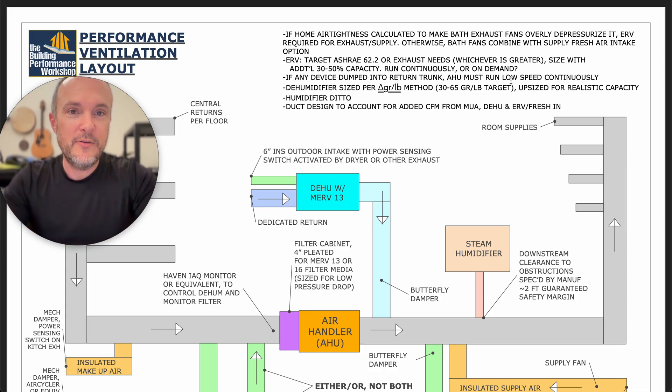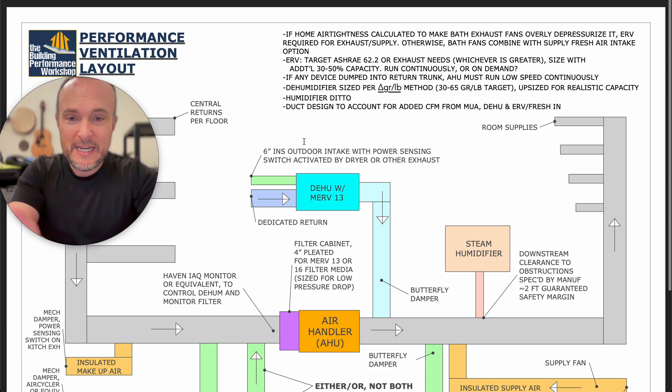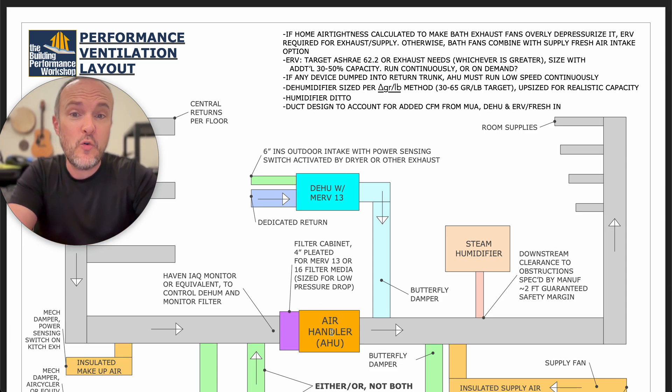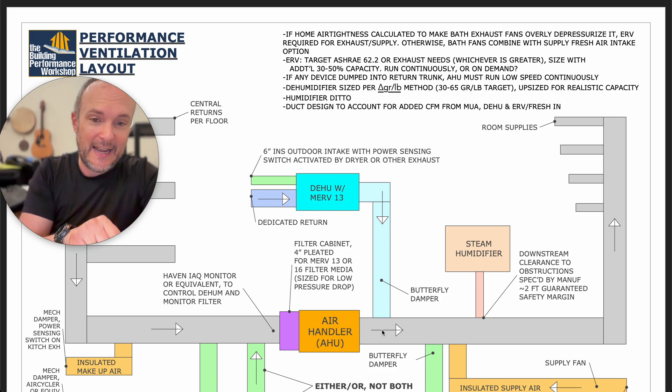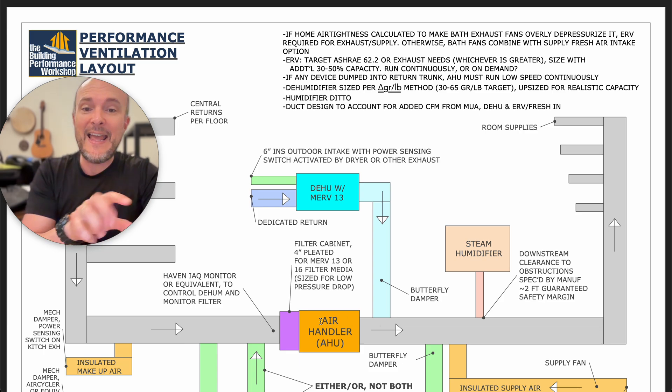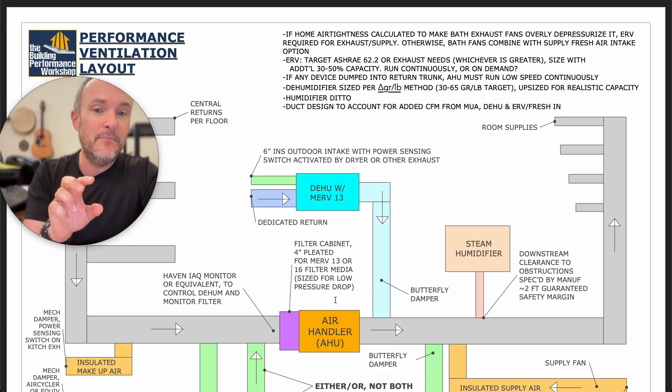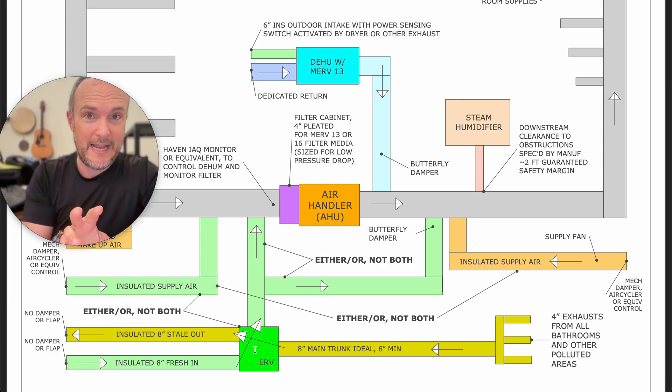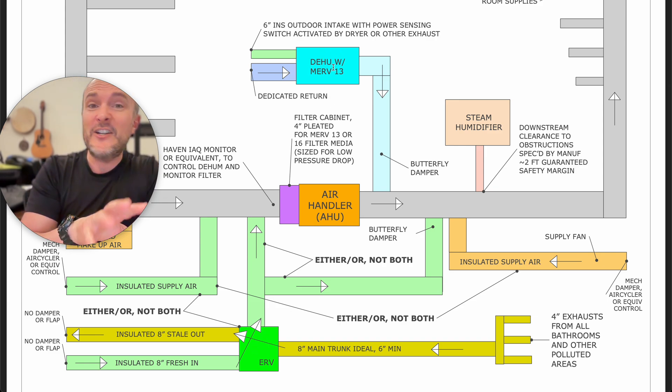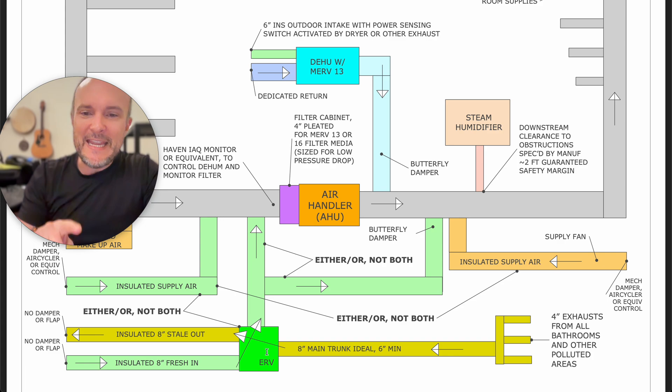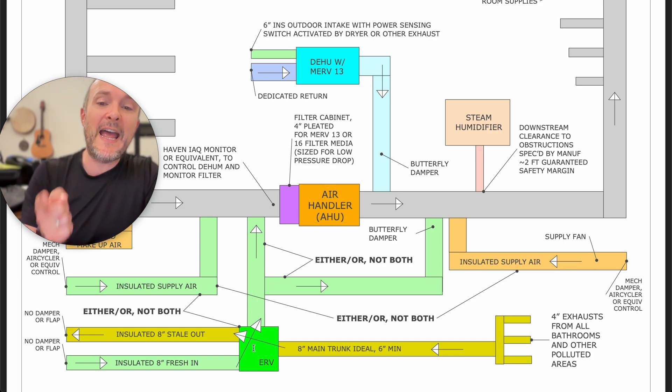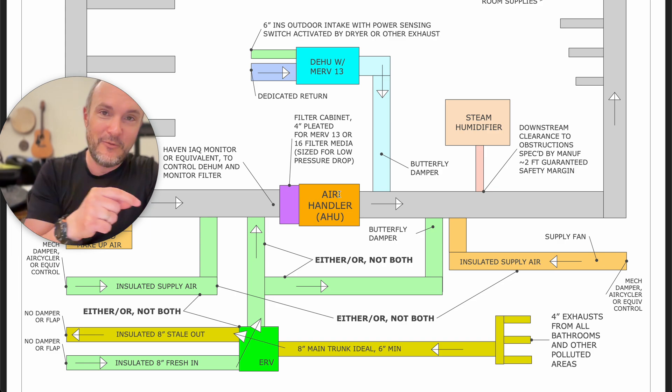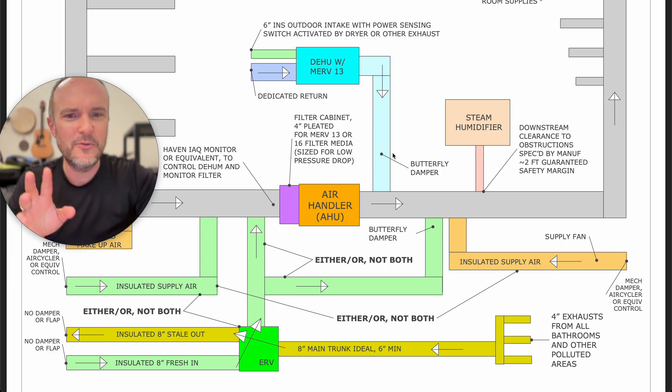That sounds like it's a cool idea, and I just wanted to run through how that would work. Here is the way that it works now: the air handler has a coil in it that's supposed to be cooling and drying. We dump the dehumidified air into the supply side because then this thing can cool and dry and we're not stealing away the ability for it to dry. So then this dehumidifier is supplemental, not the primary. The ERV gets dumped into the return so that we can have one filtration level inside the box and one filtration level here right before the air handler.